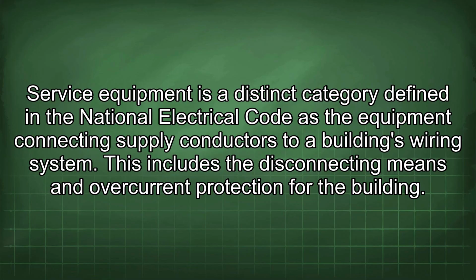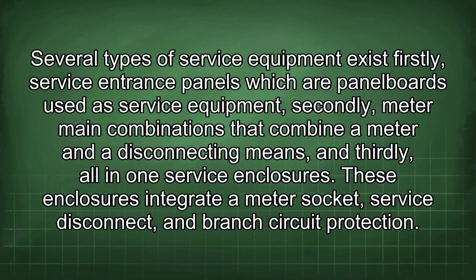Service equipment is a distinct category defined in the National Electrical Code as the equipment connecting supply conductors to a building's wiring system. This includes the disconnecting means and overcurrent protection for the building. Several types of service equipment exist.